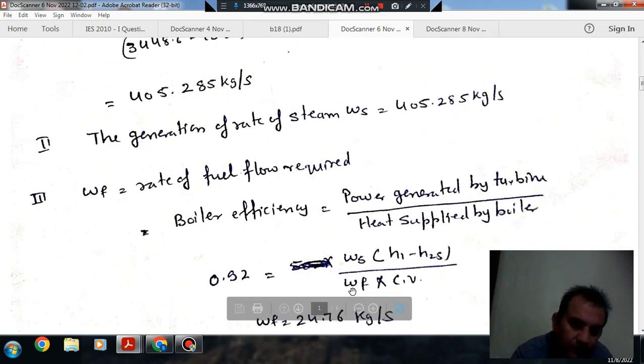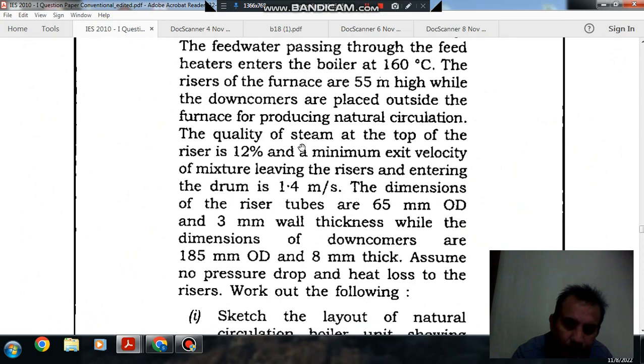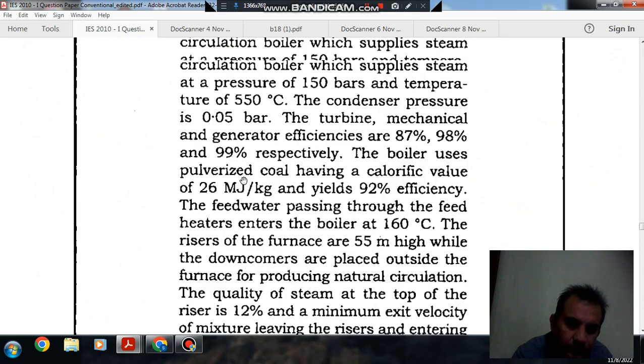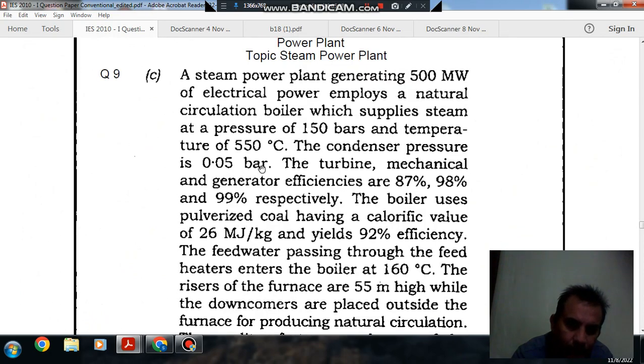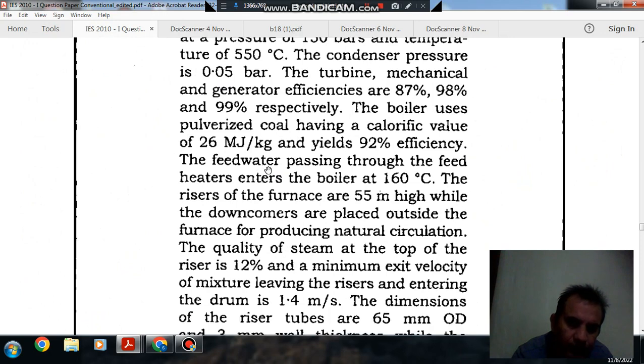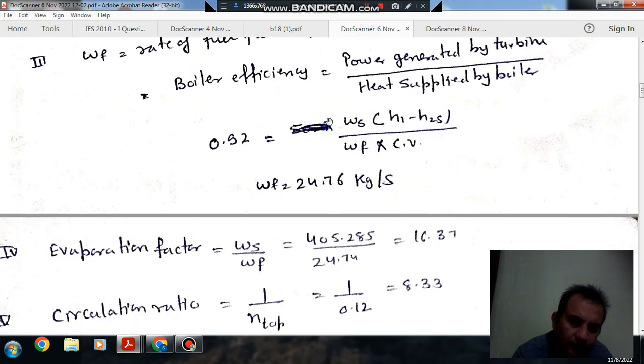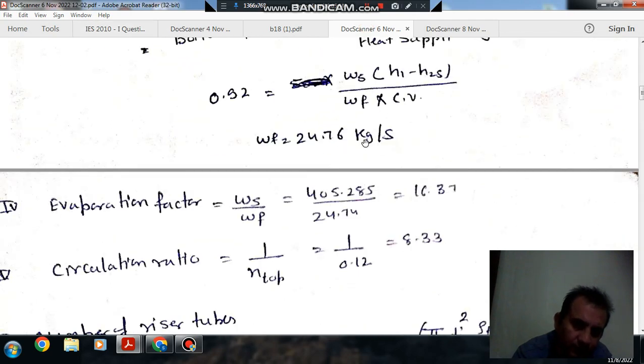Next is to find fuel flow rate. Heat supplied by the boiler is omega F into calorific value. Omega F is what we have to find out and calorific value is 26 MJ and boiler efficiency is 92%. We can find out omega F comes out as 24 kg per second.